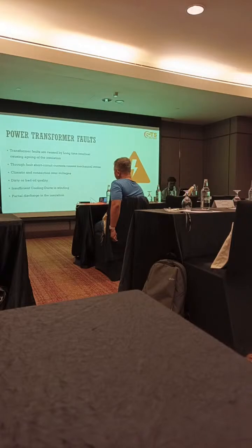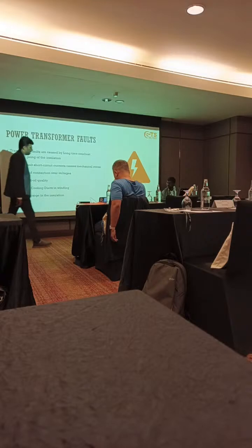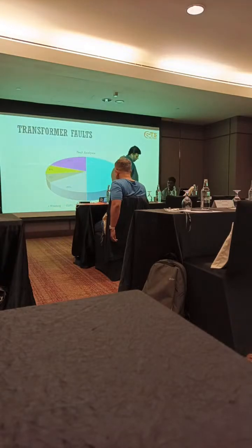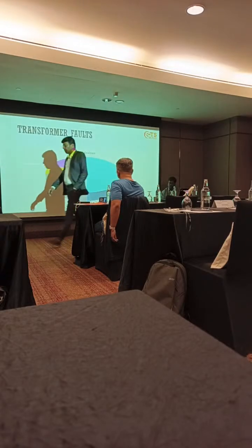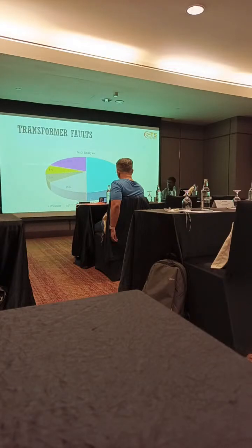Then the partial discharge, the latest one: partial discharge in the insulation of the transformers. That's also another case. And this is the one which causes faults. Once the fault happens, the transformer has failed. So this is the general analysis.